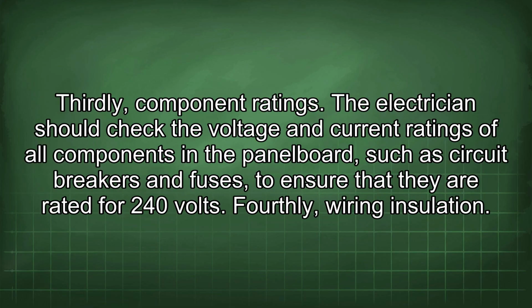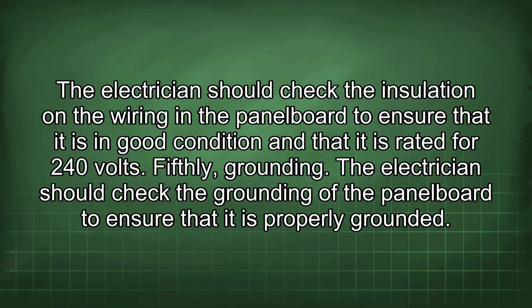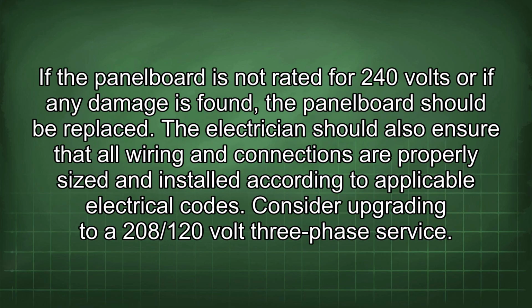Thirdly, component ratings. The electrician should check the voltage and current ratings of all components in the panel board, such as circuit breakers and fuses, to ensure that they are rated for 240 volts. Fourthly, wiring insulation. The electrician should check the insulation on the wiring in the panel board to ensure that it is in good condition and that it is rated for 240 volts. Fifthly, grounding. The electrician should check the grounding of the panel board to ensure that it is properly grounded. If the panel board is not rated for 240 volts or if any damage is found, the panel board should be replaced.